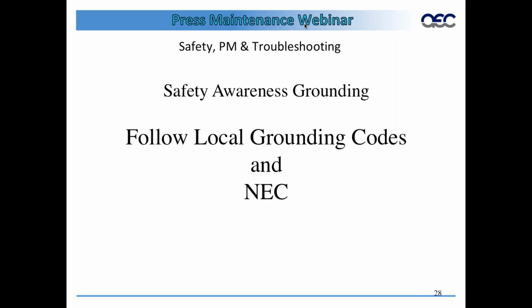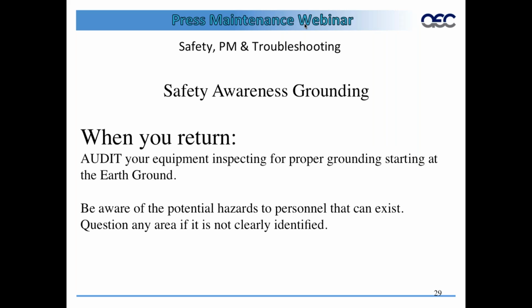So follow all the local grounding codes and the NEC, and they're very specific, and they guide you through how things should be. So when you finish, or at your next available PM, or right away, go out and do an audit.